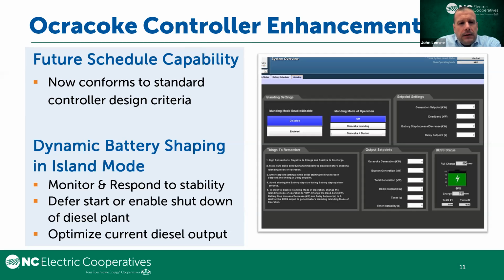They said it'd be real nice to be able to set parameters based on the load to bring the diesel on and to levelize the output, and then use the battery to dynamically follow the load. So we brought together our operations team and our engineering team and did a control system modification where we're able to use the battery to dynamically load follow. We call it the single island or the 2-island mode, either in support of Ocracoke Island alone, or feeding back up through the submarine cable to the larger Outer Banks, where we've got another set of diesels.